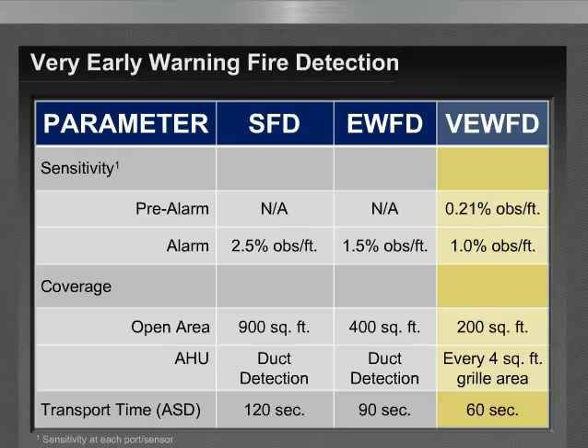And similar to the other sensitivity classifications, when we look at aspirating type smoke detection systems, we'll have that category of transport time. And you've seen it go from 90 seconds for early warning fire detection down to 60 seconds for very early warning fire detection.